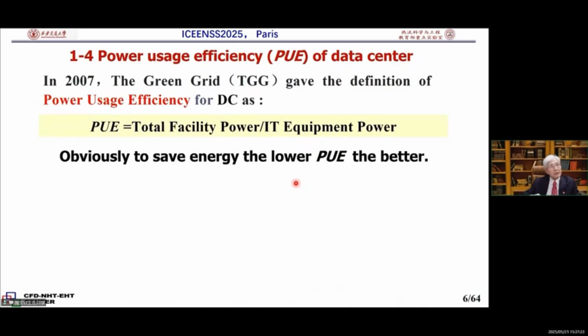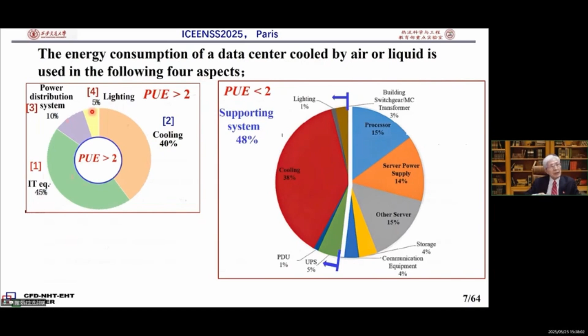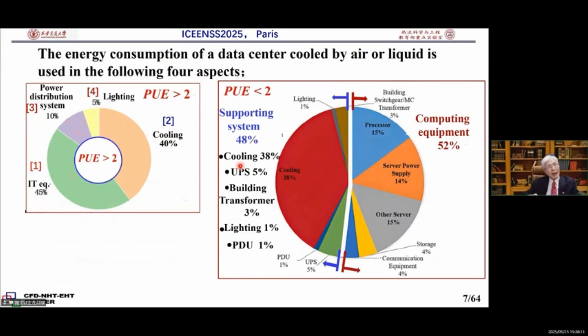The energy consumption of a data center is used in the following 4 aspects. First, IT equipment. Second, cooling. Third, power distribution system. Fourth, lighting. This is for PUE larger than 2. For PUE less than 2, the supporting system, including cooling, UPS, building, transformer, lighting, PDU, and computation equipment on the right-hand side is about 52%.